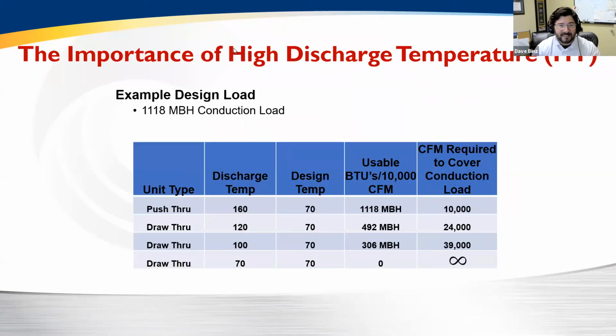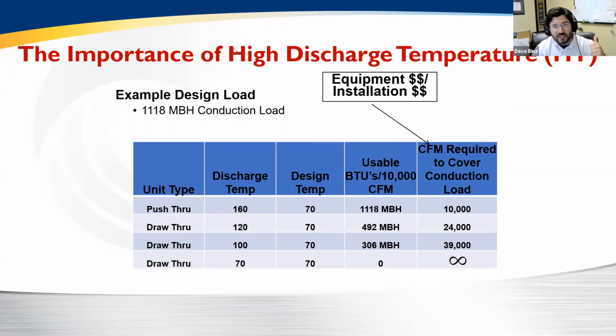So why is 160 important? Because if I have that 1.1 million BTU conductive load, only the available heat above space temperature can counteract that skin load. So if I, for instance, were using a low temp draw through unit and I was limited at 120 degrees, I would need 24,000 CFM to meet that skin loss.